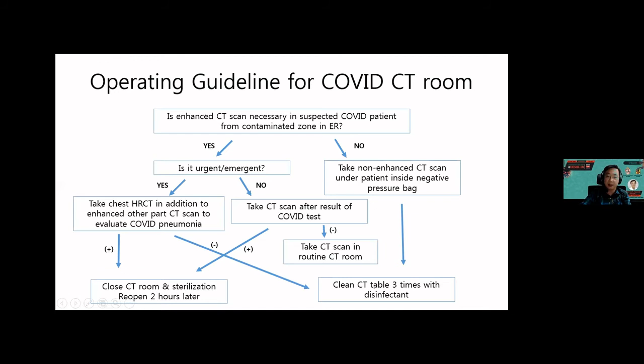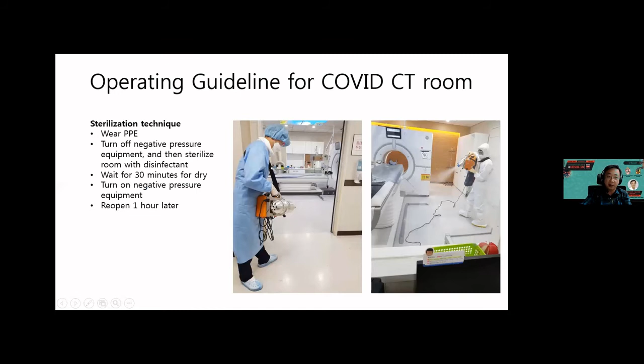If the COVID CT room is exposed to virus, immediately close the CT room and sterilize it. Healthcare workers should wear PPE like this and turn off the negative pressure equipment, and then sterilize the room with disinfectant and wait for 30 minutes to dry. And then turn on the negative pressure equipment, and we can reopen 1 hour later.